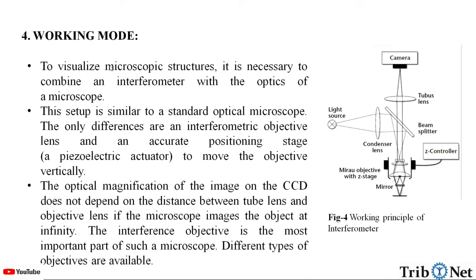Let us understand the working mode of the interferometer. To visualize a microscale structure, it is necessary to combine an interferometer with the optics of a microscope. This setup is similar to a standard optical microscope. The only differences are the interferometer objective lens and an accurate positioning stage — that is, a piezoelectric actuator — to move the objective vertically. The optical magnification of the image on the CCD does not depend on the distance between the tube lens and objective lens if the microscope images the object at infinity. The interference objective is the most important part of such a microscope, and different types of objectives are available.